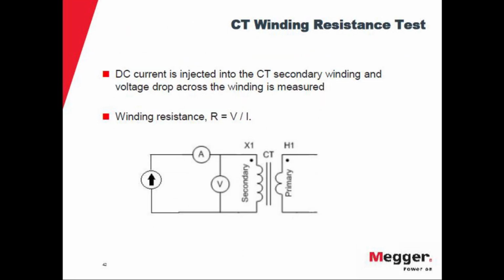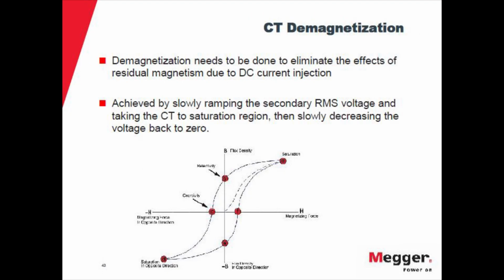Here you have the winding resistance. So you connect to the secondary winding of the CT, and you measure the winding resistance. So pretty much the same concept that we were talking about before with the low resistance meter, with a little bit of the effect of the winding, not so high here. We'll talk about the inductive effect later. And then because you are using DC current here, this core is going to get magnetized. So that has to be demagnetized so it doesn't affect the other tests that you need to perform.